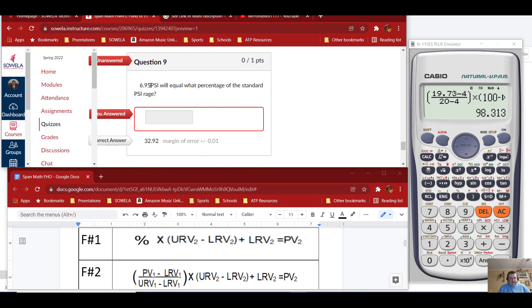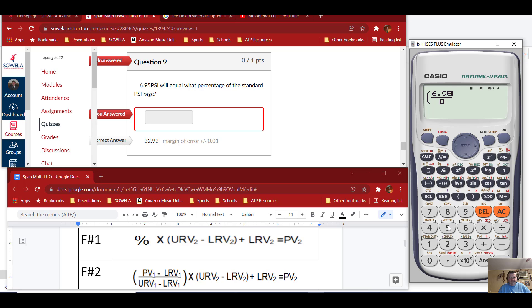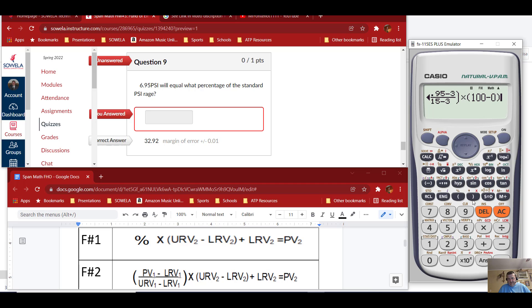Number 9: 6.95 psi — that's the 3 to 15 range. Open parentheses, over-under: 6.95 minus 3, over 15 minus 3. Close parentheses, times, open parentheses. What percentage? 100 minus 0, plus 0. Gives me 32.92%, rounded to two decimal places.